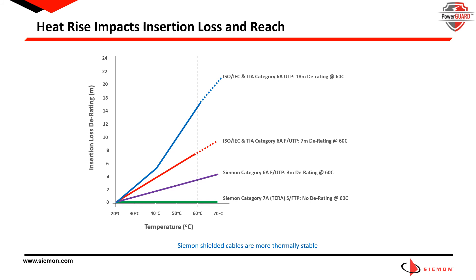There are some key cable features and characteristics that result in less heat rise and therefore less derating and bundling restrictions. First, larger conductor gauges exhibit less heat rise, which is why Category 6A and 7A exhibit less temperature rise than Category 5E or 6. Secondly, overall shielded cabling offers better heat dissipation — in fact, shielded cables exhibit half of the heat buildup of UTP. And finally, cables with a higher operating temperature, like Siemon's 75°C-rated Category 6A and 7A cables, are more thermally stable and offer better heat dissipation.